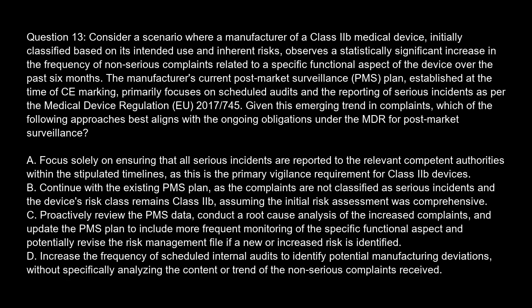Question 13. Consider a scenario where a manufacturer of a Class IIb medical device, initially classified based on its intended use and inherent risks, observes a statistically significant increase in the frequency of non-serious complaints related to a specific functional aspect of the device over the past 6 months.